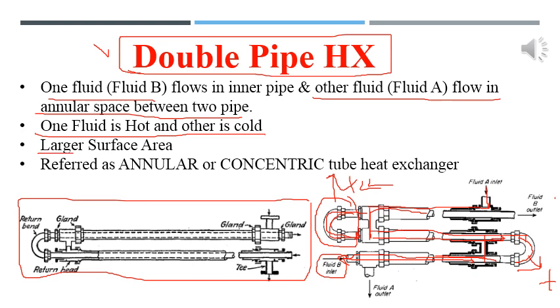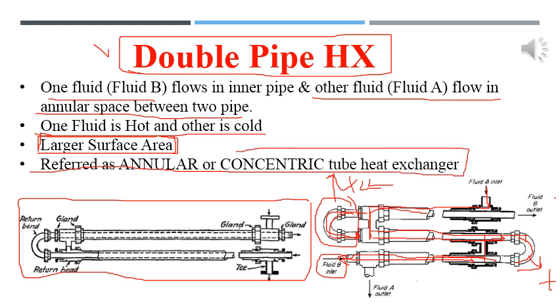The double pipe heat exchanger consists of two concentric pipes — an outer annular pipe and an inner pipe — arranged in a concentric configuration. The hairpin sections can be connected in series or parallel to provide more heat transfer surface area. More hairpins are required if larger heat transfer area or larger heat transfer services are needed. If the hot fluid is passed through the annulus, insulation of the outer pipe is needed, which adds cost. The solution is to introduce the hot fluid in the inner pipe and the colder fluid in the outer pipe — this way, insulation cost is negligible.